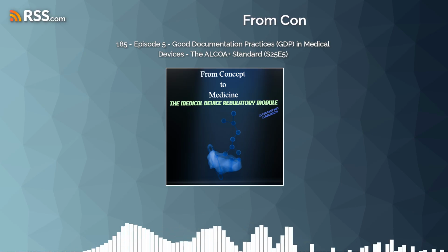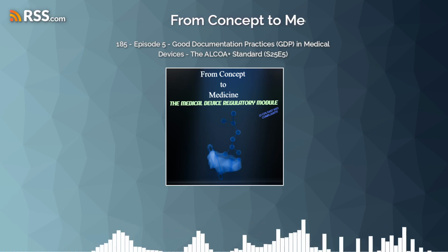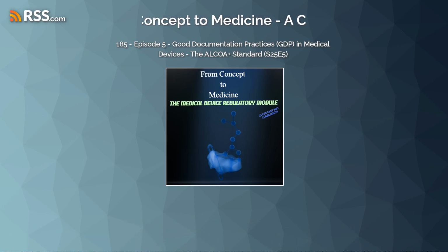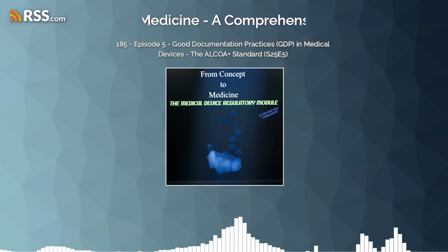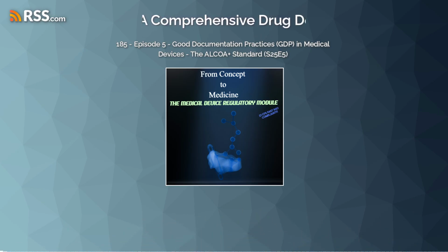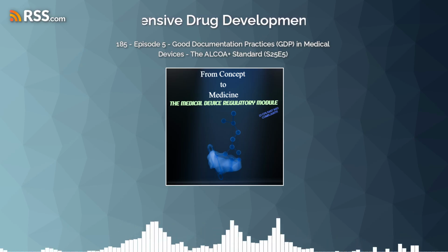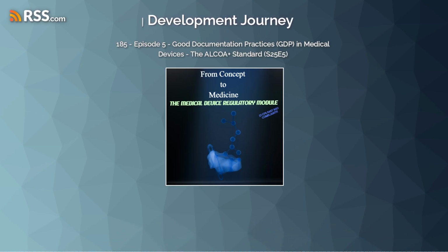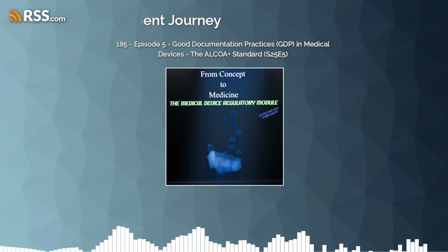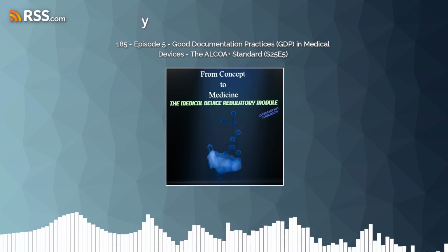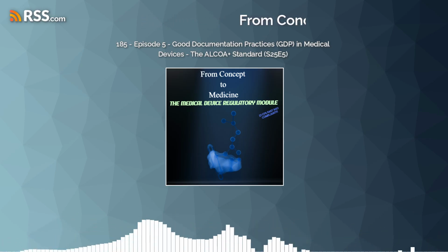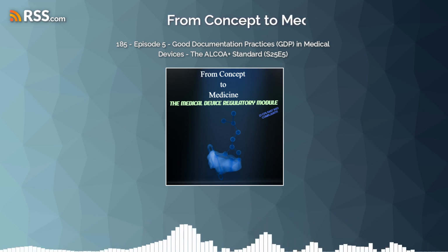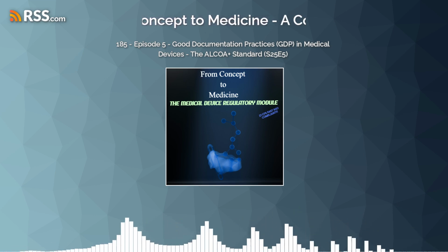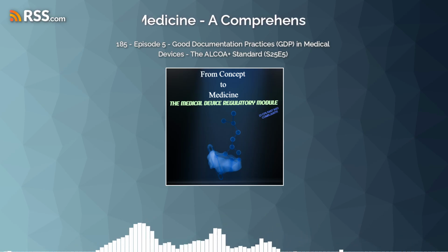dictates what goes into the DMR, which is the master instruction set on how to build it consistently. Okay. And finally, the DHR provides the proof, the record, that each specific batch or unit was actually built following those DMR instructions, thereby fulfilling the design intent from the DHF. Right. It connects the design intent to the actual product. Exactly.